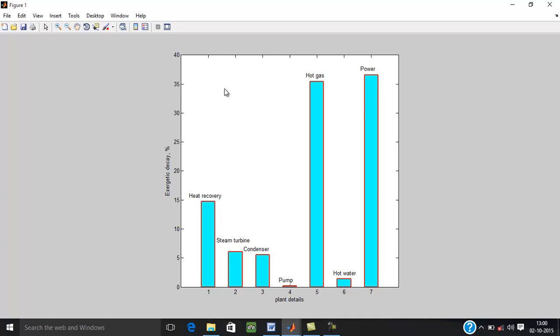The power output 36.6%. This shows hot gas is the weakest area so that there is a scope to improve, that is minimize this hot gas irreversibility loss by decreasing temperature. The second scope is heat recovery. A properly designing pinch point, this can be minimized.